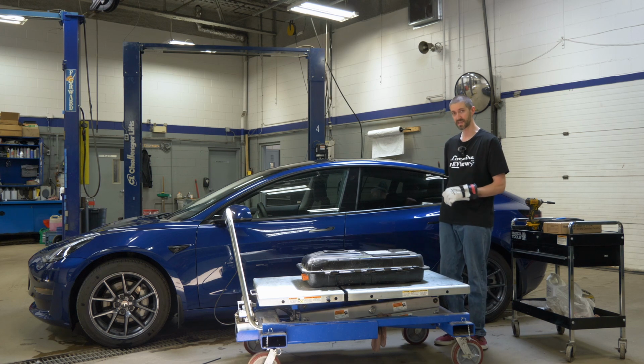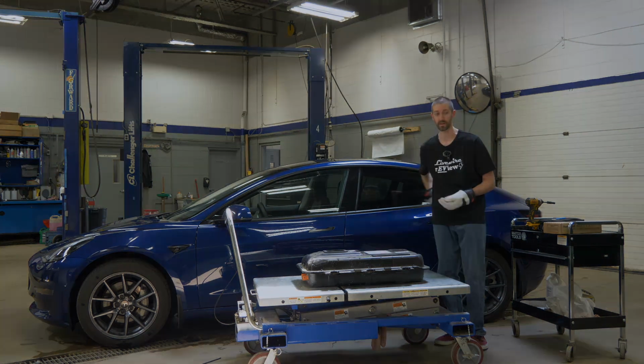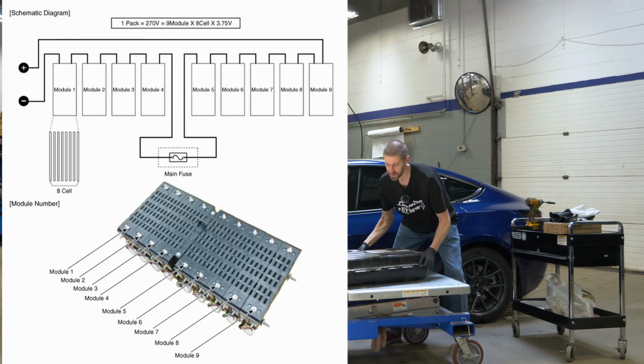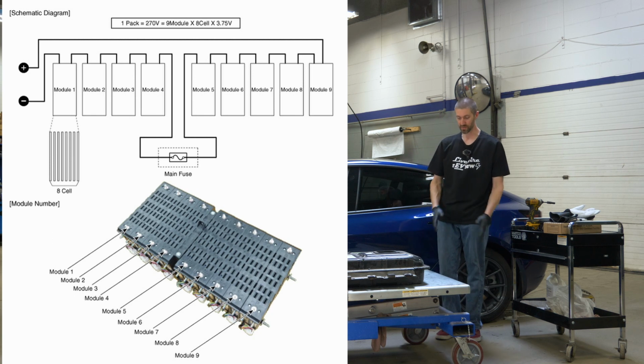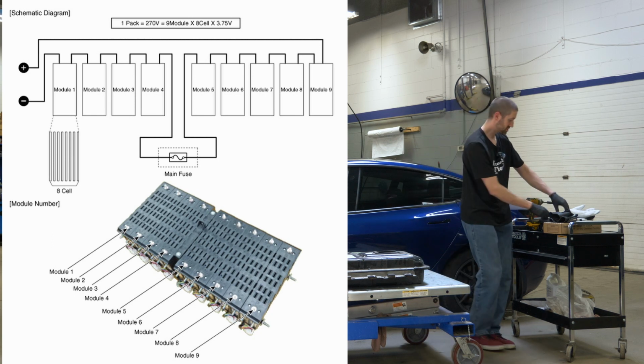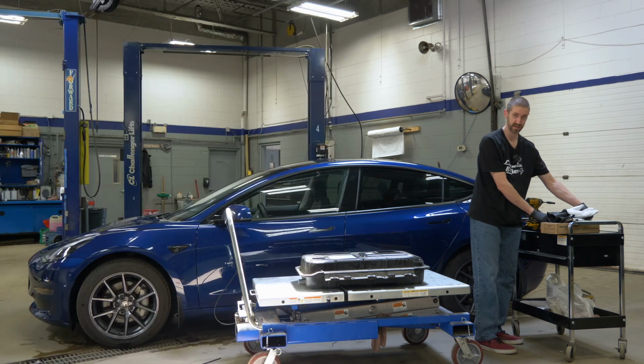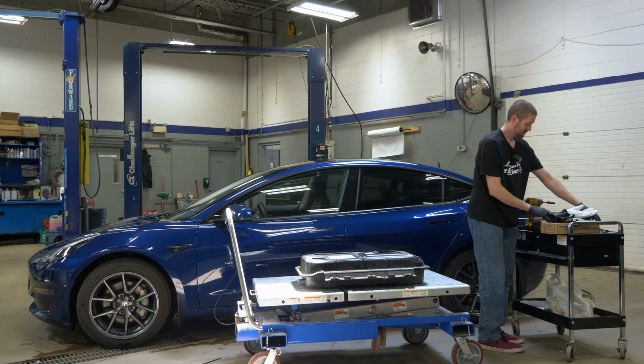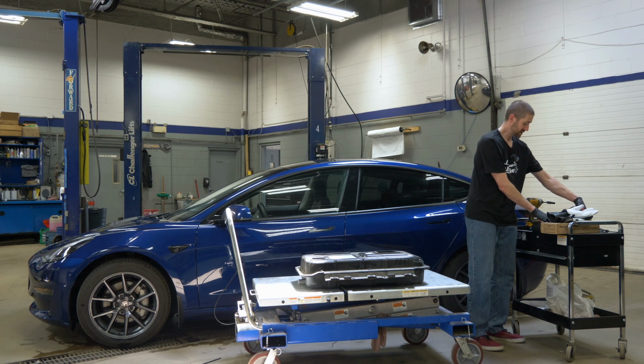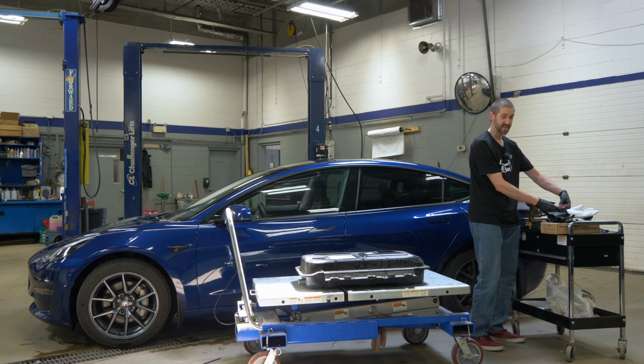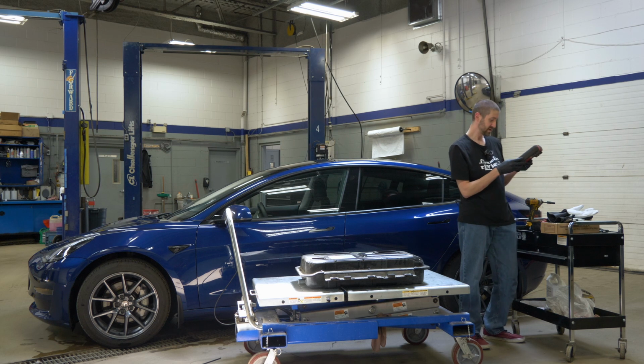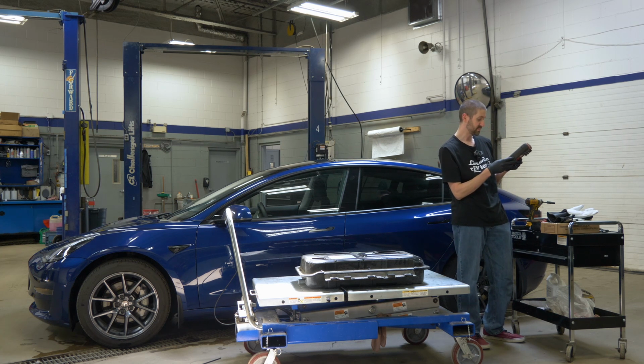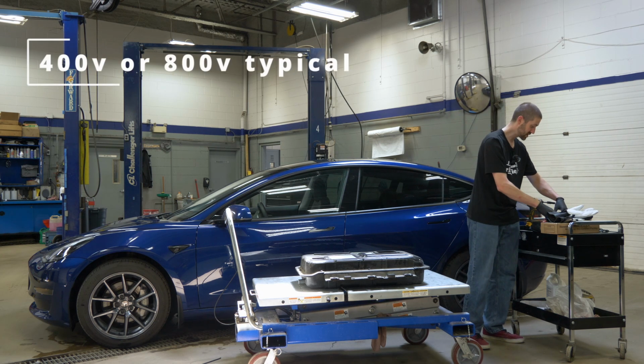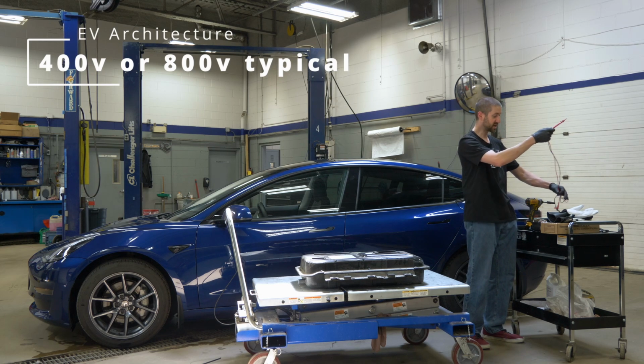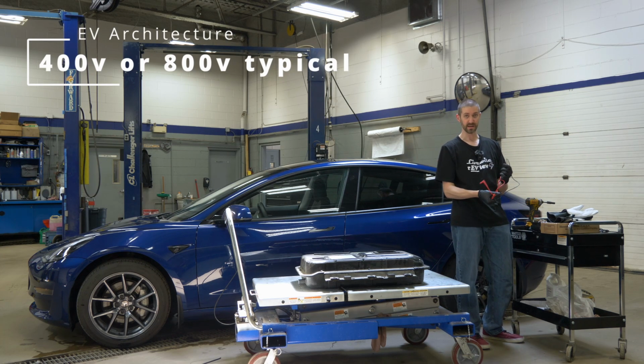So we're going to take a measurement and see how many volts are coming out of this battery before we start. Okay, so this one's a hybrid battery, and this one has a certain number of cells that add up to 270 volts. So out the end here, we should be measuring 270 volts. Give me a second here to set up my meter. When choosing a meter for this task, make sure you pick one that is rated up to 1000 volts DC. And on here, let's read it. It says Category 3 max 1000 volts DC. You must pick this because certain systems are up to 800 volts and the test is actually done at 1000 volts.